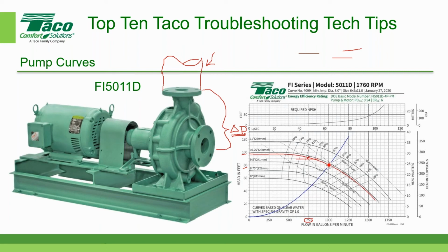Let me erase some of these lines because it might be a little bit too confusing. So I'm going to go 90, this is 90, and I'm going to go just above that and draw a horizontal line, and that's going to intersect the pump curve. And so they're telling me that they measured 92 feet, and that's how they came up with 750 gallons per minute.